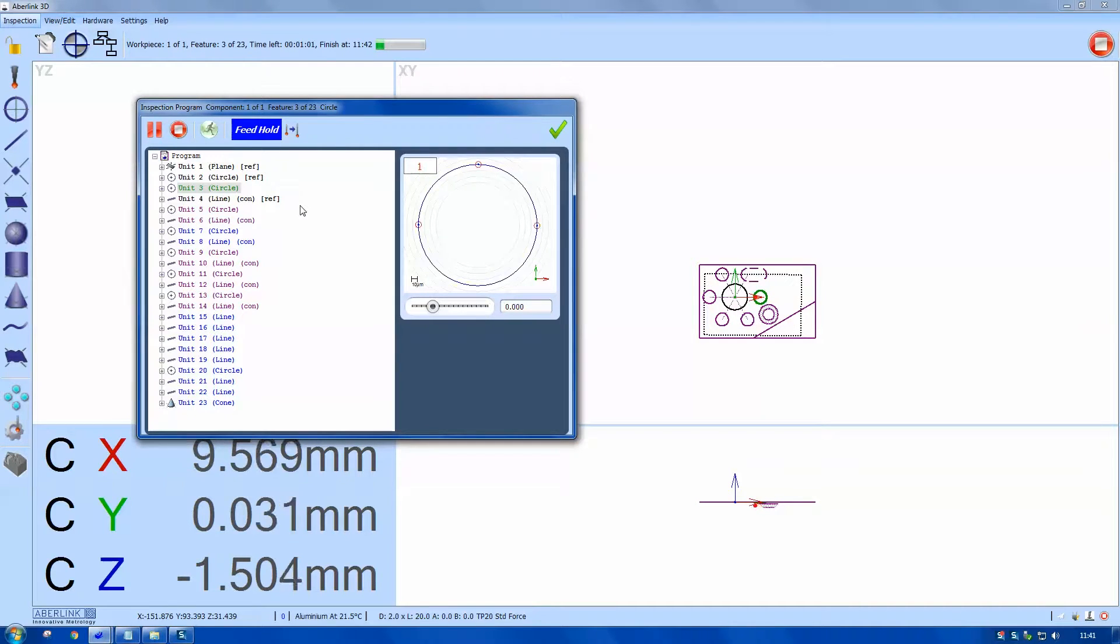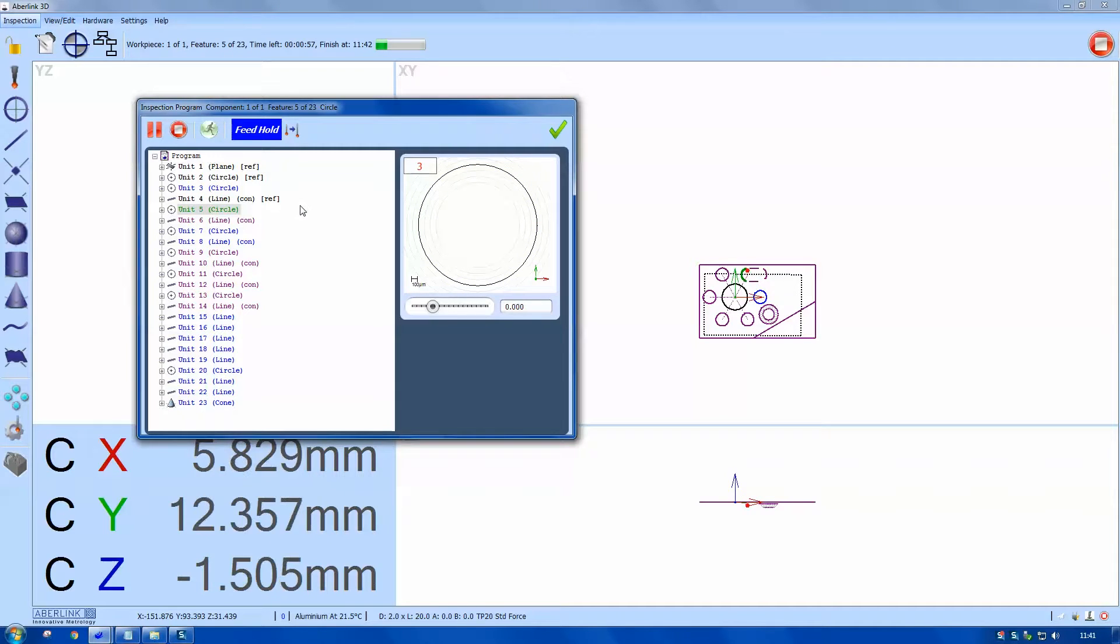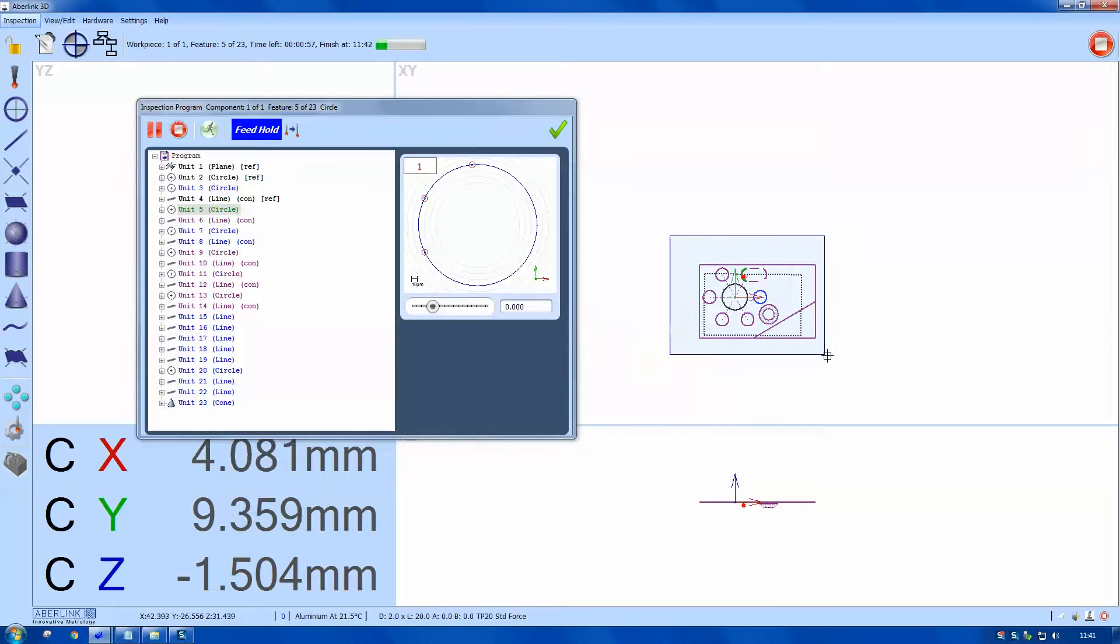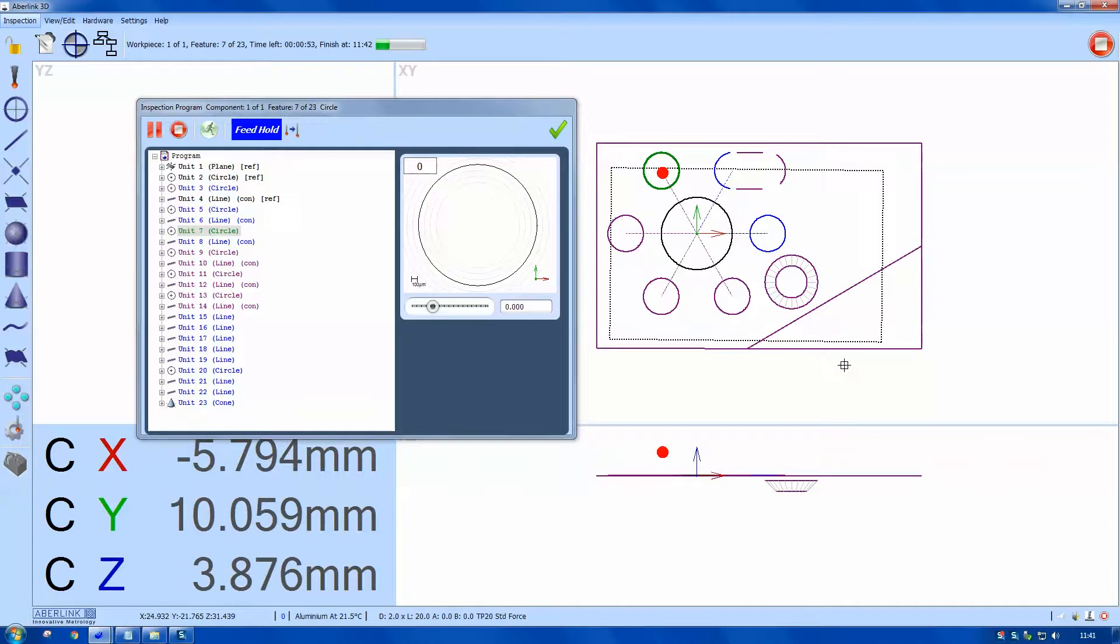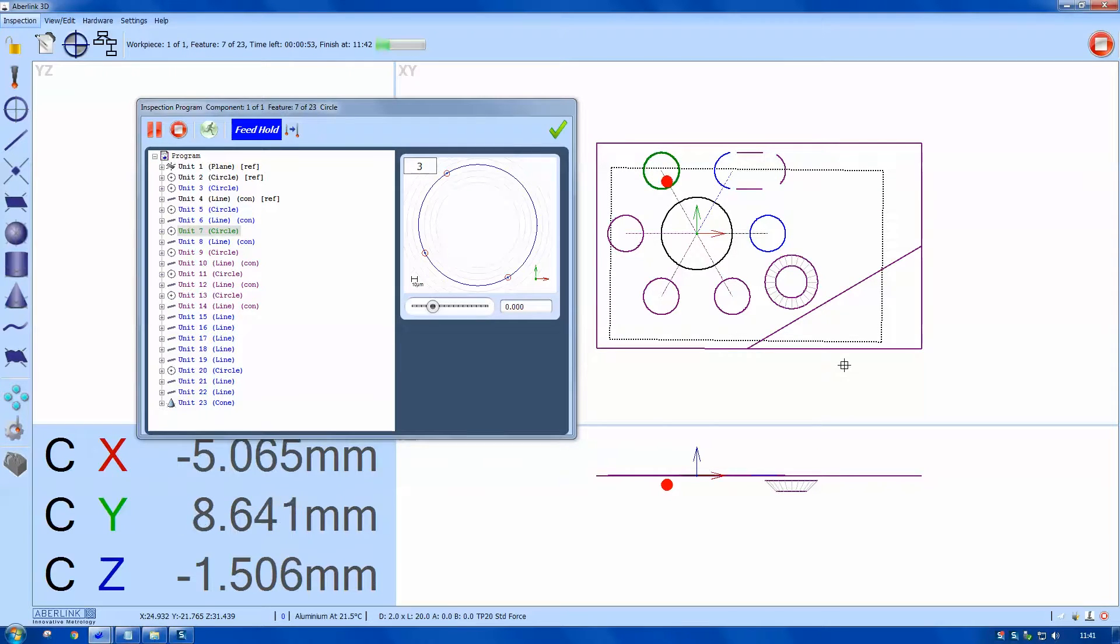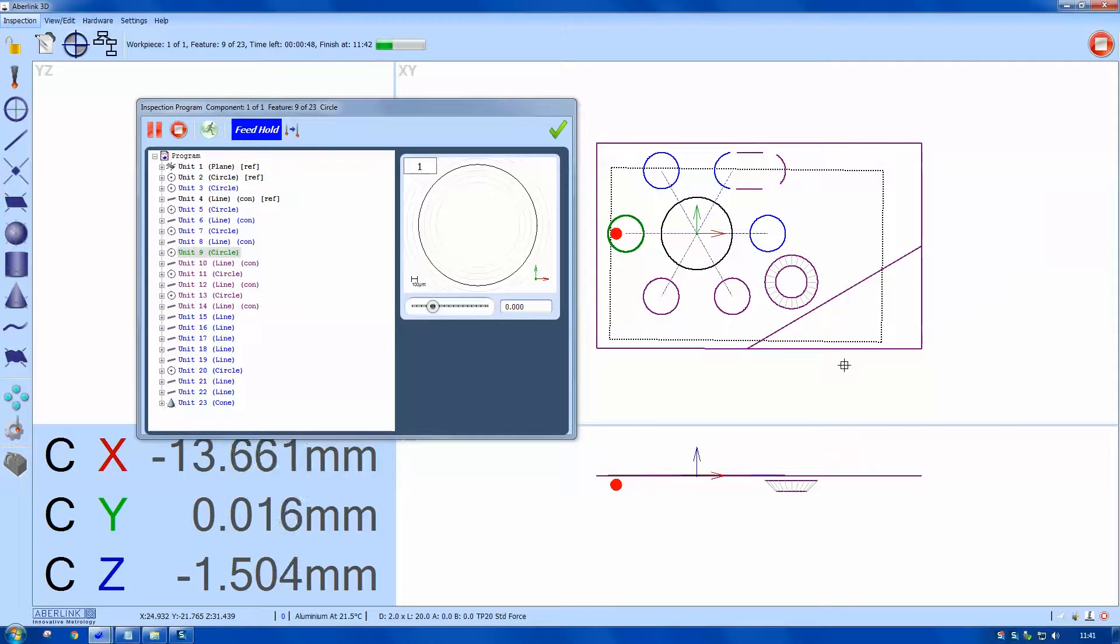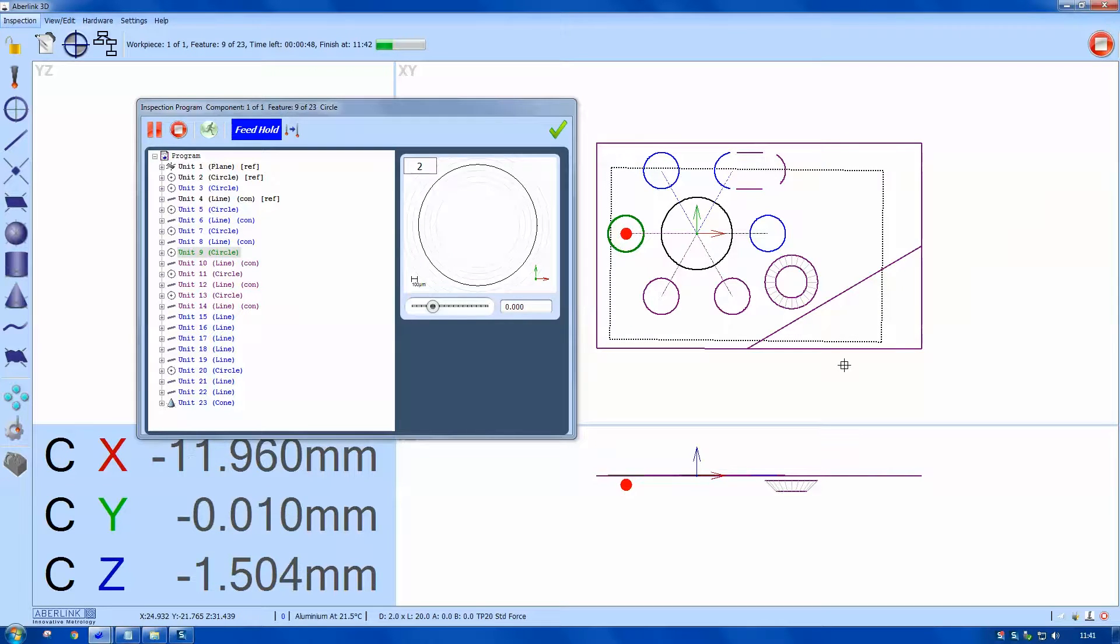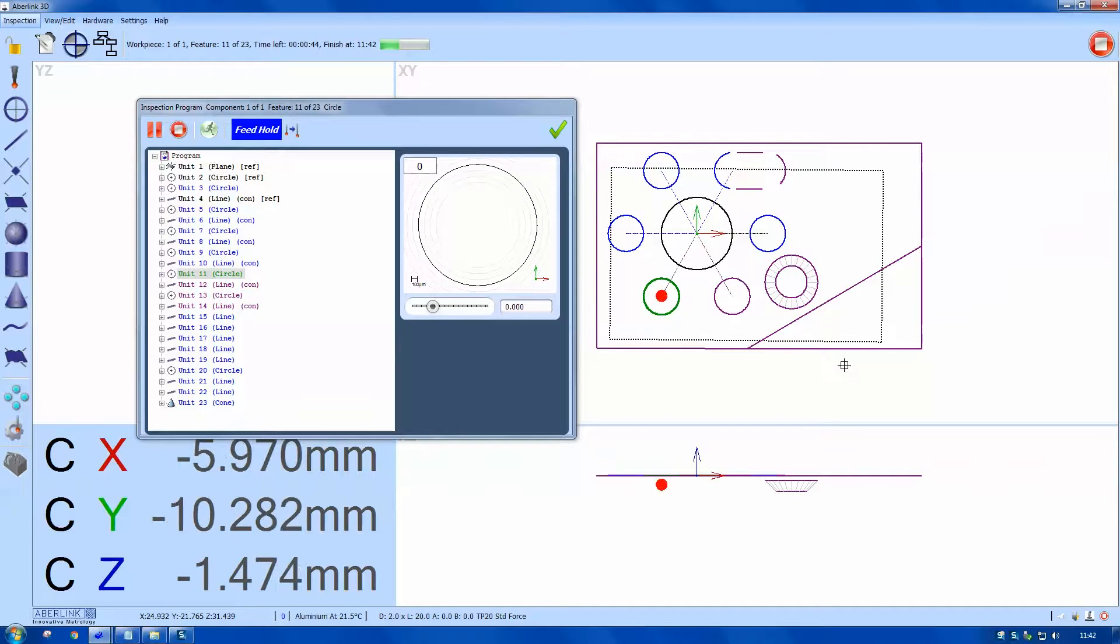This is also a good tool for dry runs. You can see on the screen the next feature is highlighted green. You can actually see the probe on the screen probing the feature. On the left hand side of this list, you can see what's been measured and what's the current feature.